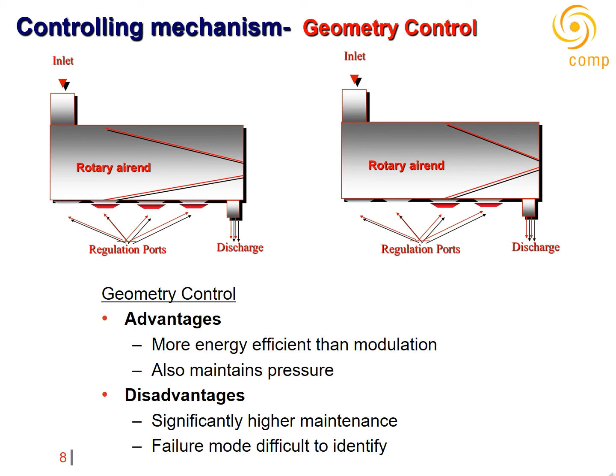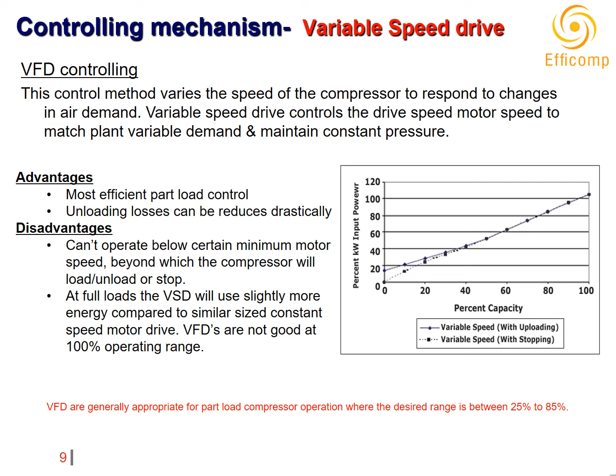This control method varies the speed of the compressor to respond to changes in air demand. Both lubricated and oil-free screw compressors can be purchased equipped with variable speed drive controls that continuously adjust the drive motor speed to match the variable demand requirements and maintain constant pressure. These compressors usually operate in on-off or load-unload control when air loading drops below the minimum speed of the drive. In most cases, a variable speed drive compressor offers the most efficient part load operation. Ideally, when there are multiple air compressors at a facility, one or more fixed speed compressors would supply the base load compressed air and a VSD compressor would be used to supply the fluctuating or trim load.